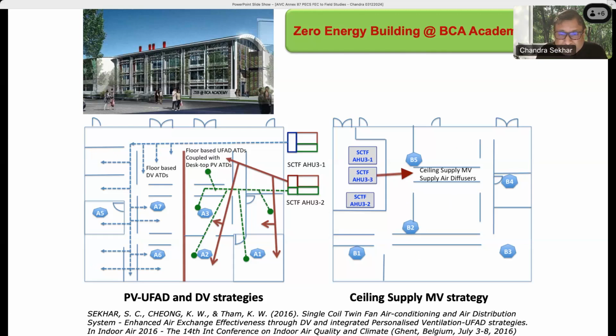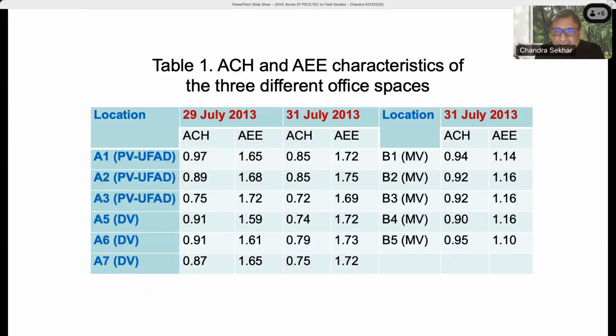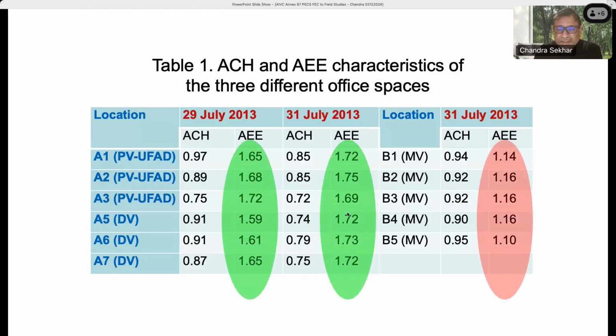We were trying to measure the air exchange effectiveness, or ventilation effectiveness characteristic. You notice the green shaded region—these are the AEE values when personalized ventilation with underfloor air distribution was used, or displacement ventilation alone, and they were significantly higher, which we would expect, showing the benefits of such systems.